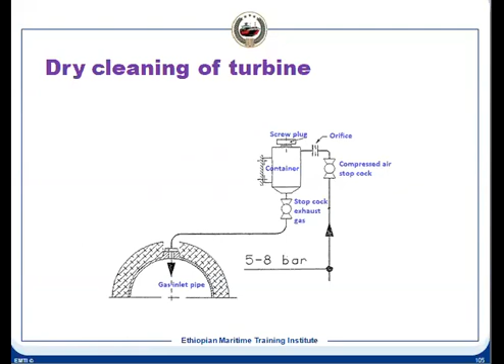Somebody else also raised a hand. Tell me. Because that will make the imbalance more adverse. The situation will be worse because once you do the cleaning, some deposit will come out, some deposit will not come out, and it will make the rotor imbalance more. So that will be a dangerous situation. So then you will have to remove it, do the overhauling, and it can become unbalanced, and then clean and box back.